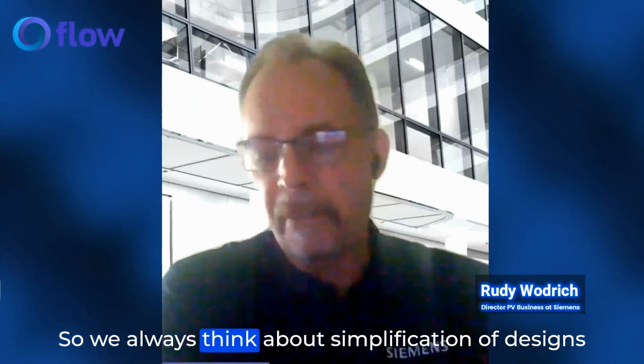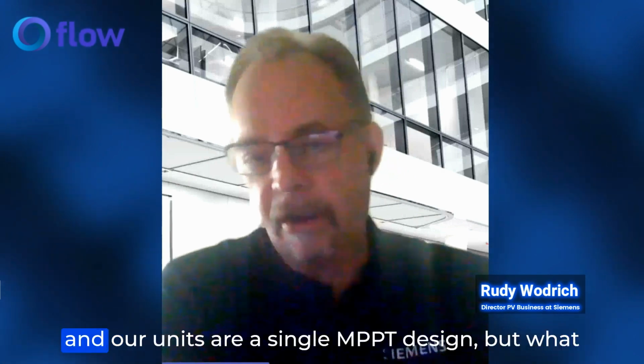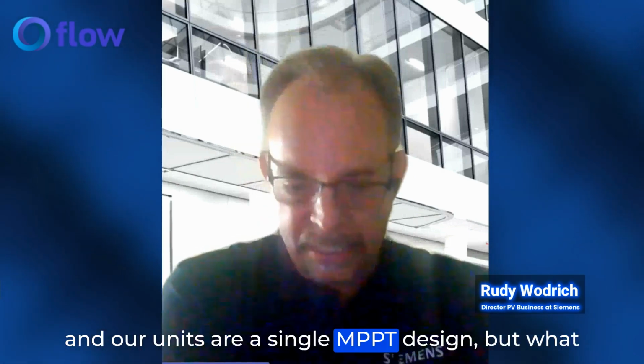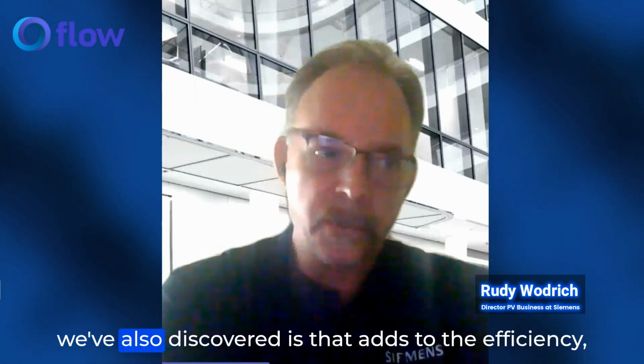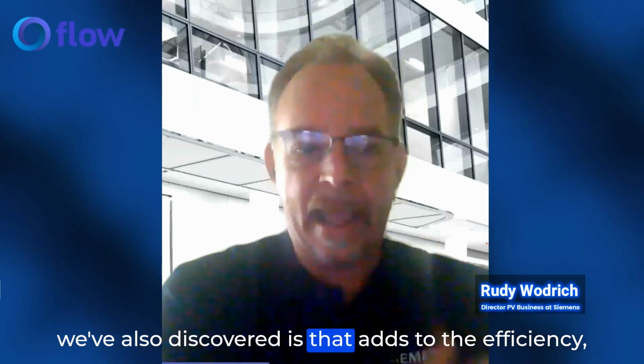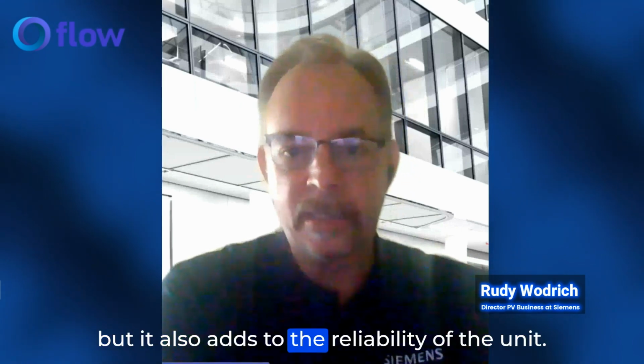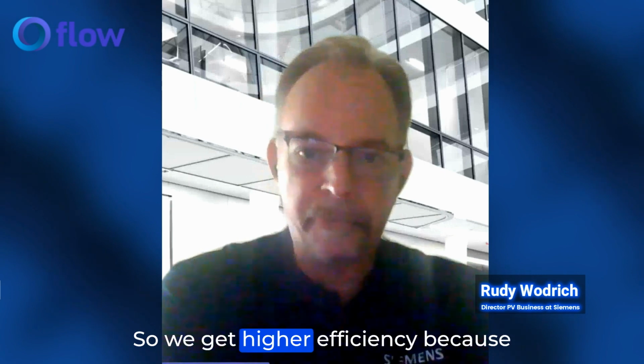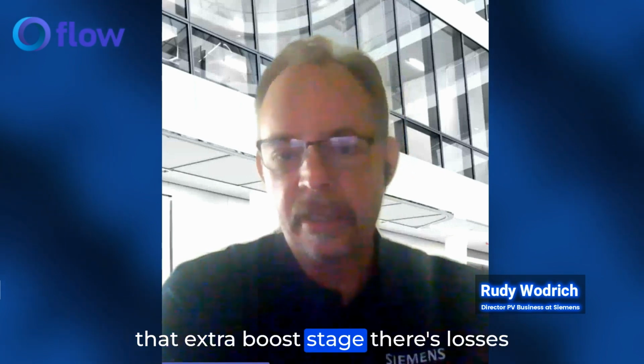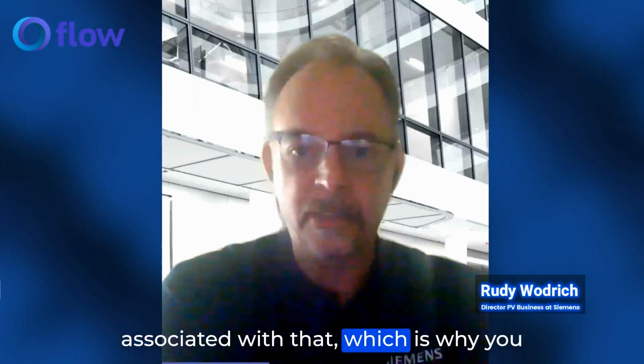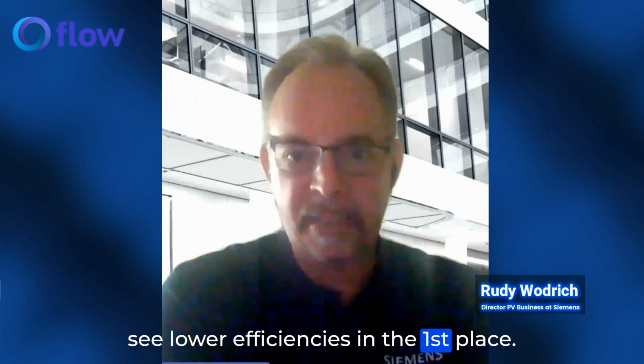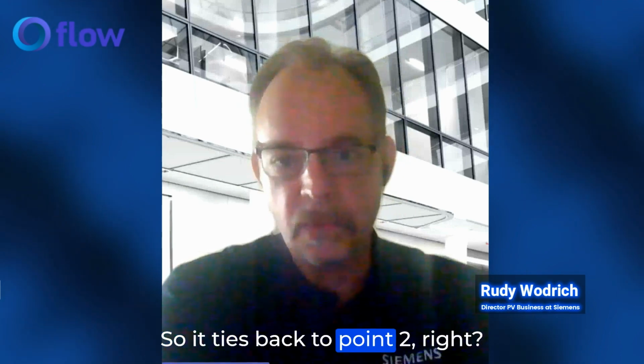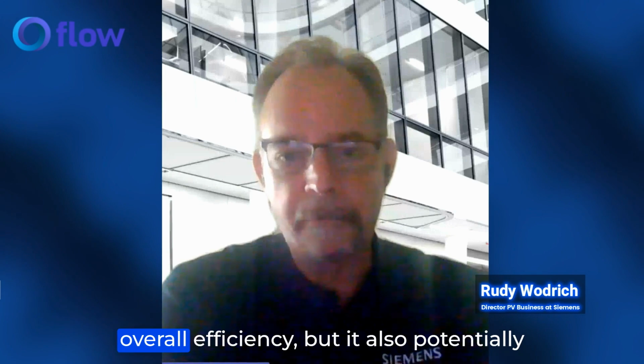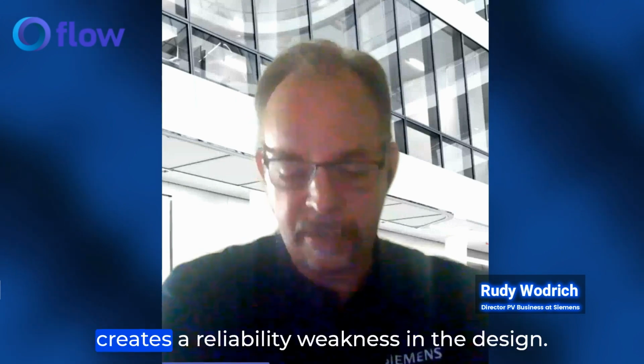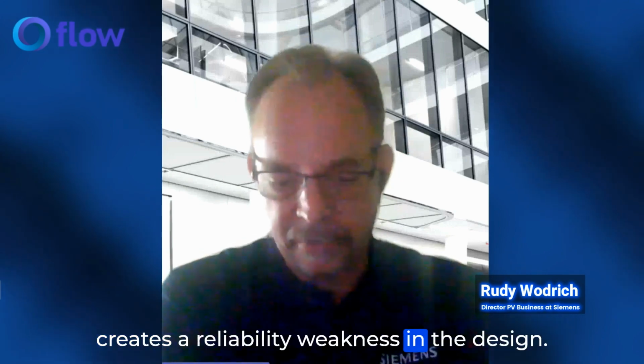We always think about simplification of designs, and our units are a single MPPT design. What we've discovered is that this adds to efficiency, but also adds to reliability. We get higher efficiency because that extra boost stage has losses associated with it, which is why you see lower efficiencies in multi-MPPT units in the first place. It ties back to the overall efficiency point, but it also potentially creates a reliability weakness in the design.